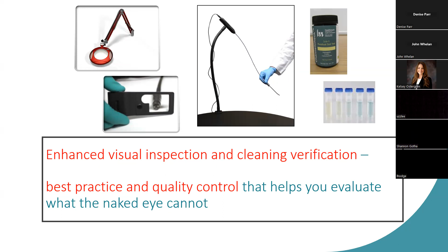All the current national standards are consistent in calling for active drying after processing, even after the AER. What's done in the AER is a purge of air. It's not meant to be a validated drying cycle, and the scope still remains coiled while it's lying in the AER. So anybody that's ever pulled a scope out of an AER knows that you hold it up and water drains out. So what we're talking about with the drying is external surface drying with low-linting or lint-free cloths and having filtered air blown through the channels. This should be outside of the AER, even when the AER has an air purge or extended dry time. For AORN, this needs to occur whether the scope is headed right to another procedure or whether it's headed to storage.